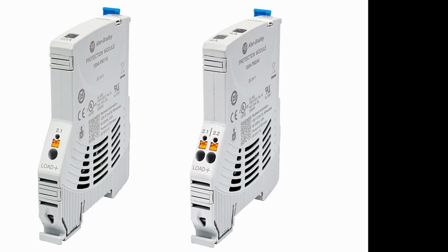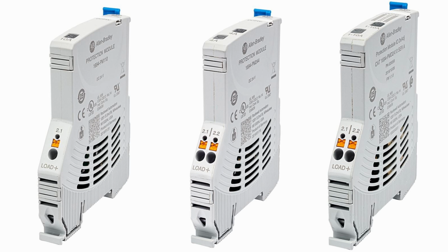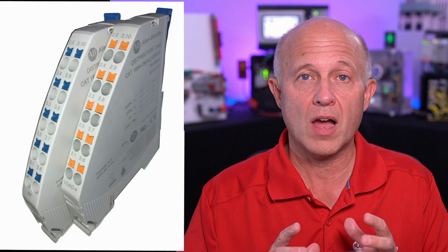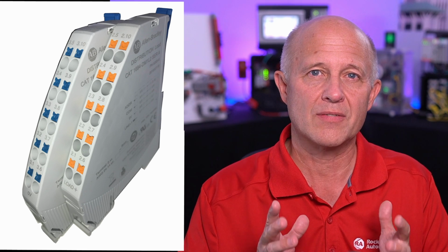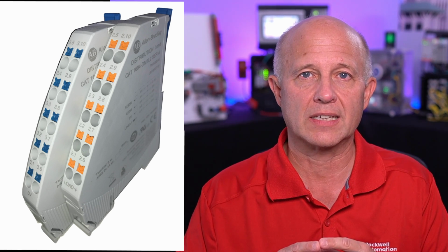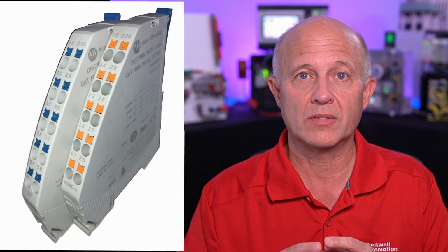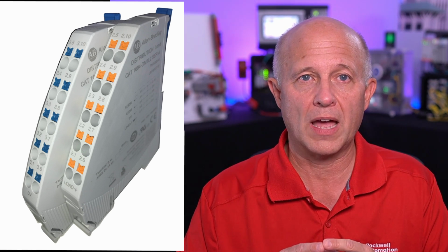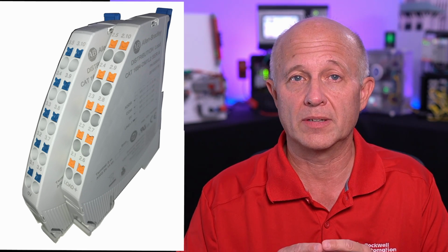There are three models of the protection modules available: single or space-saving dual-channel modules that have fixed current ratings from 1 to 10 amps, and the dual-channel adjustable model that gives you the flexibility to program each channel from 1 to 10 amps in just one device. In addition to the two main components, there are optional power distribution models that kind of act as terminal blocks for connecting multiple devices on one channel or to feed 24 volt power downstream to another control cabinet.